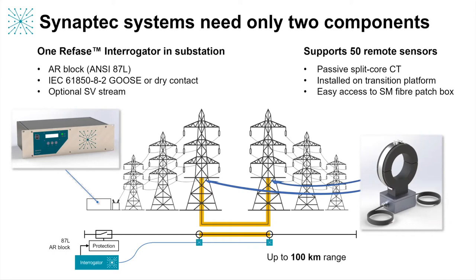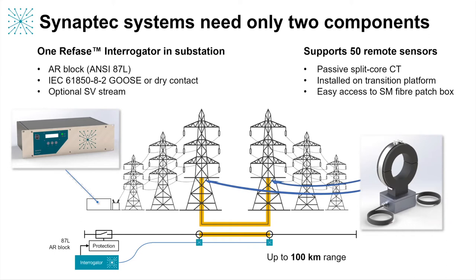Optionally, we can also make available high resolution sample value measurements from all sensors to the operator, time-stamped with respect to GPS. It's also important to note that if there's a loss of time synchronization — if the GPS receiver is malfunctioning — all the measurements performed by the interrogator remain in relative sync, so the monitoring scheme is not compromised and still operates fully. These sensors are completely passive, using Synaptec's unique and patent-protected optical measurement technology. In contrast to other fiber technologies, we use an industry standard split core CT to perform the primary conversion.